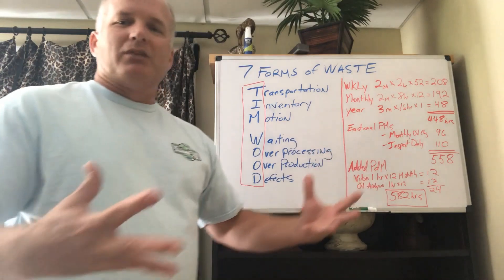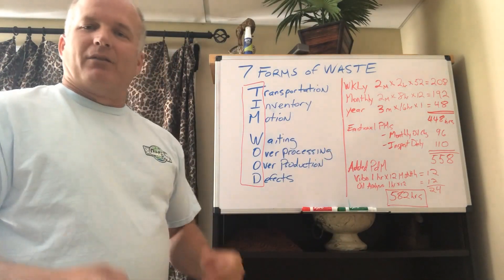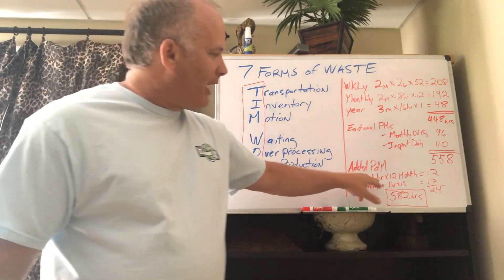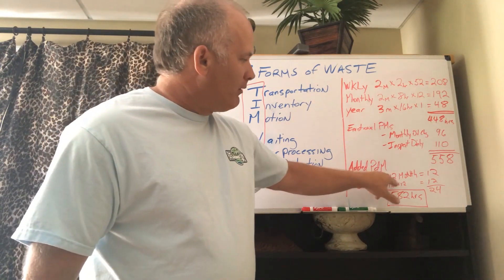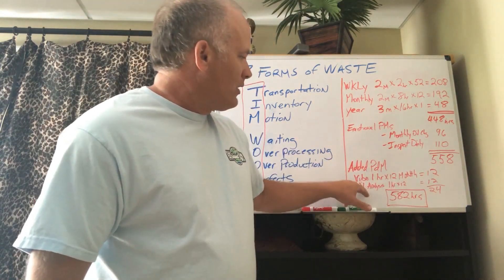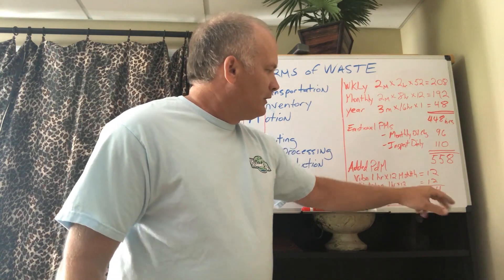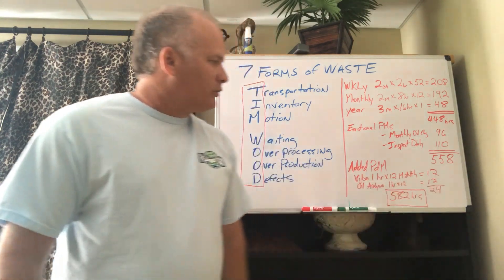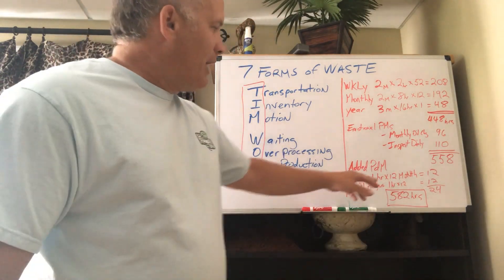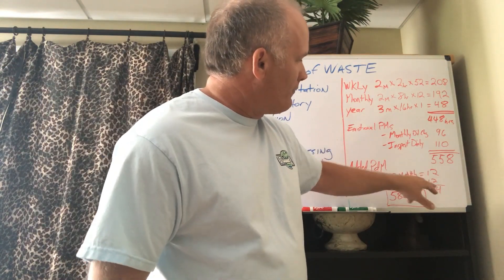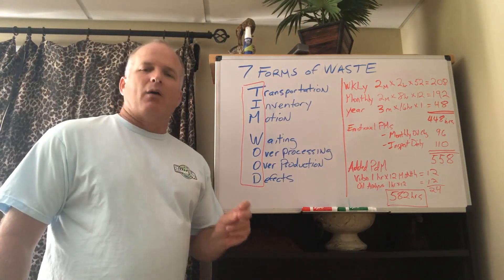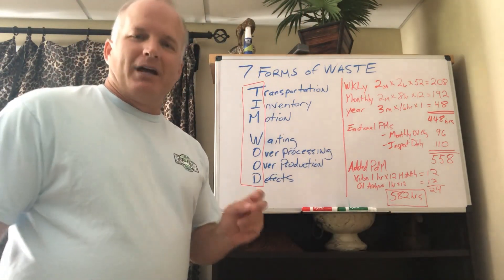Then PDM — condition monitoring — came along. We got some new tools and added a vibration route: one hour, once a month, 12 months — 12 hours. Plus oil analysis — 12 hours — for a total of 24 PDM hours annually. So you add up the investment: 558 plus 24 gives you 582 hours invested in that asset. The critical problem: we added condition monitoring on top of time-based maintenance and never looked at them as one integrated program.